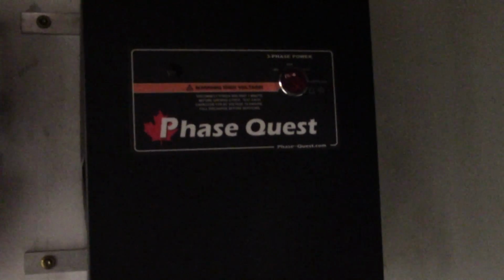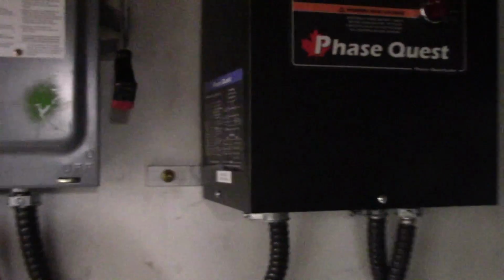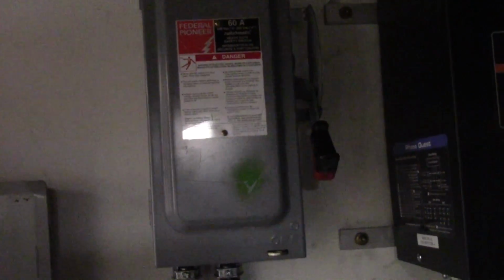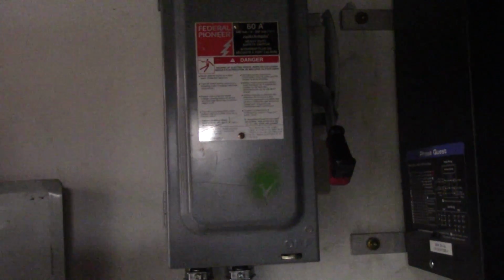This is Phase Quest, which is a distributor for American Rotary phase converter, and this is a 10 horsepower unit. I've got a disconnect to the transformer, so this was mandatory according to our manual there, and the little pink slip: any peripherals you have after the phase converter other than 240 volt, which that transformer goes 240 to 600, you have to put a disconnect. Or you can automate it with a timer, so when the phase converter starts up, 10 minutes, or you can make it any time you want. A few minutes after the idler winds up and is stable, then you can close the disconnect.